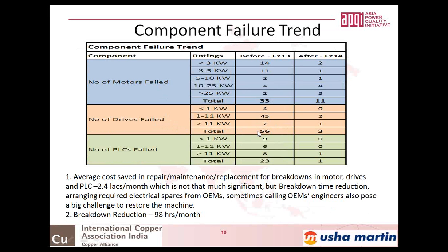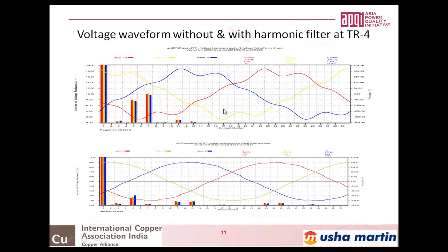And in drives, we were having a failure of 56 drives per month, which reduced to 3. Similar in the case of PLCs also. So there was a reduction in electrical breakdown of 90 hours per month, which is around 50% of our total downtime of electrical breakdowns. These were some before and after studies of the harmonic filter.